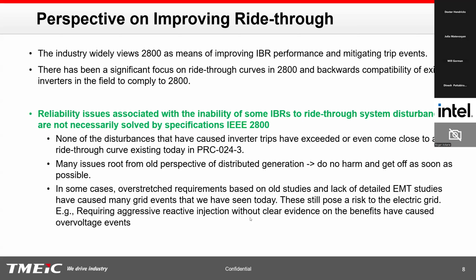In some cases, some ISOs specify very aggressive reactive injection requirements, based on studies performed a long time back, without clear evidence of how they would improve the power system. These aggressive injection functions have caused inverters to overvoltage and trip under certain scenarios during weak system events. So in some cases, the requirements can actually push the inverters to trip themselves. There needs to be an increased understanding of how these functions are to be programmed and what the trade-offs are, and they're not really discussed in 2800.